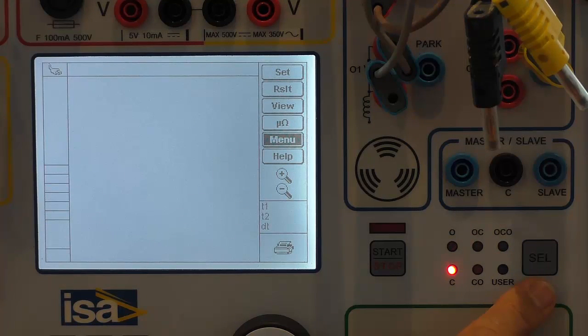The select button can be used to select the operation of the breaker. Because in this case my breaker is closed, I will select an open operation, and once I'm ready in the correct selection, I can hit the start button and the circuit breaker should open.